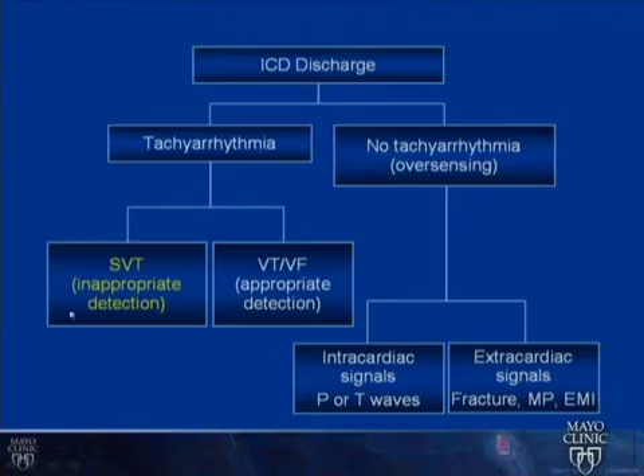So this is part of the diagnostic thinking involved: was the defibrillator discharge for a tachyarrhythmia, and if it was, was it appropriate or inappropriate? If there was no tachyarrhythmia, then the question is that the sensing part of the device was sensing something and led the device to think this was a tachyarrhythmia and therefore deliver a discharge. And the question then is, what are the signals the device may be detecting? Are these intracardiac physiologic signals, but with over-sensing, detecting P waves or T waves? Or are these extracardiac signals, and these are the times we think about lead fractures, myopotentials or electromagnetic interference.